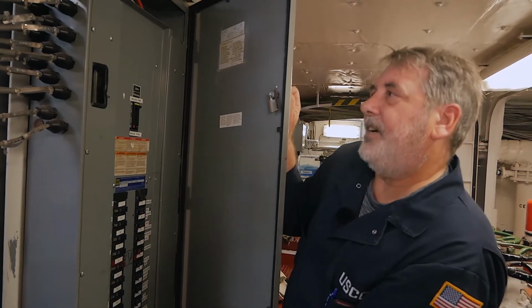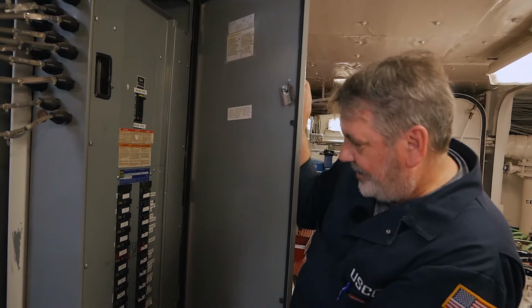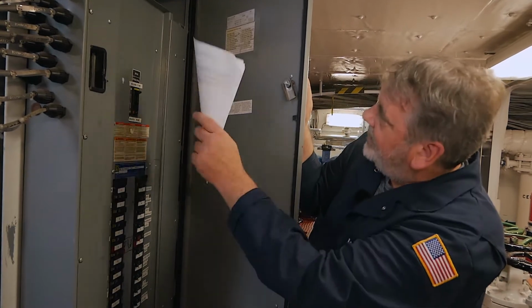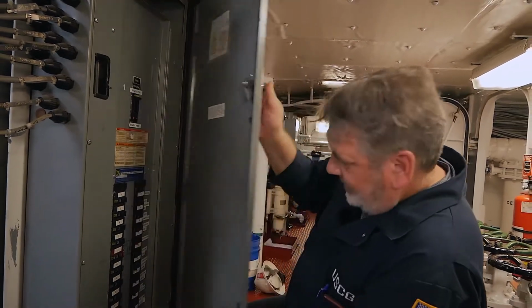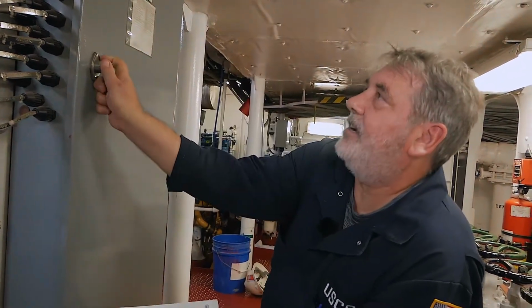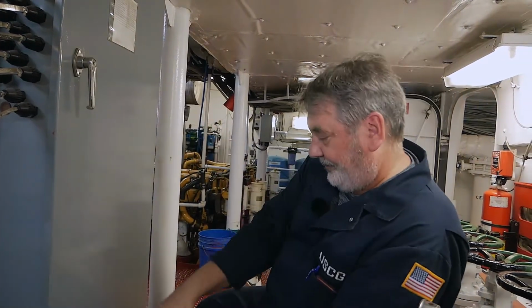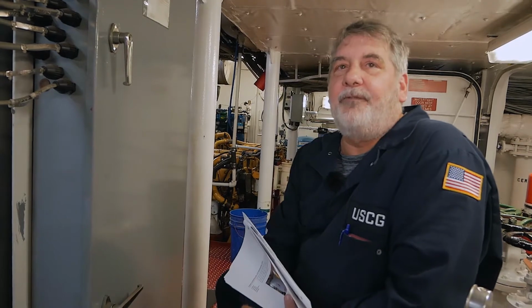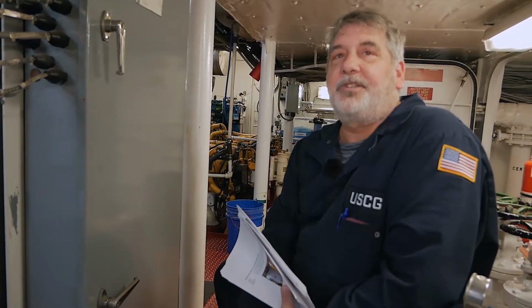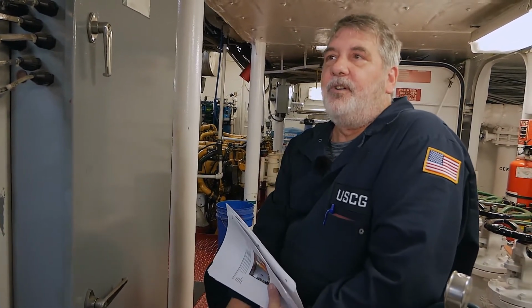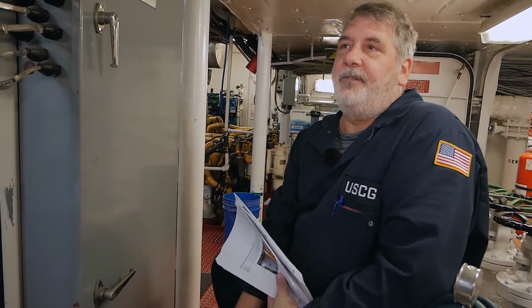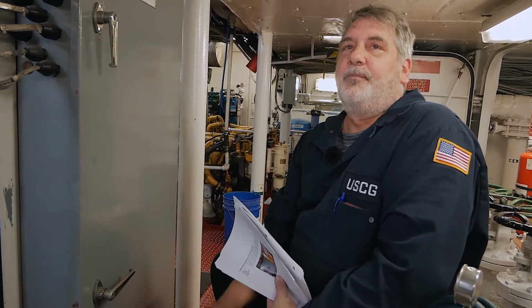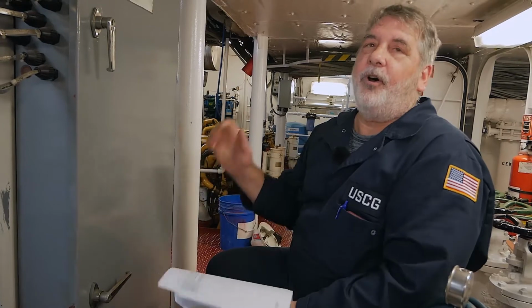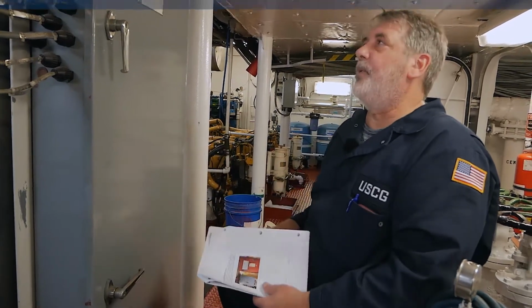That's a good set of cable entries right there. And everything is nice and squared away. I would make note that there are no electrical mats required in front of breaker distribution panels. We quite often see them in front of distribution panels, but be aware they're not required. They're only required in front of switchboards.